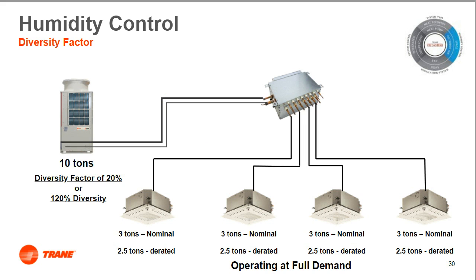As we earlier discussed diversity factor, this is important to consider when determining how your system design will function, particularly when you have zones with similar cooling profiles. Depending on a zone's exposure, an improperly sized and designed VRF system can have a negative effect on the total capacity of each terminal zone unit. If your selection does not consider the full demand capacity for the zones that experience similar temperature profiles during peak demand, de-rated factors will cause zones to be undercooled.